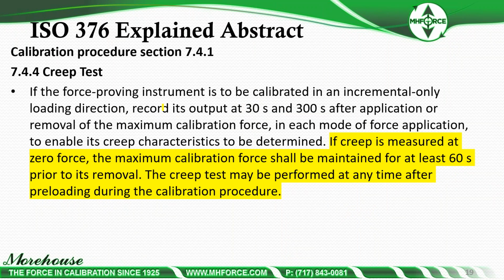Creep test. If the force proving instrument is to be calibrated in incremental loading direction only, so if we're not doing reversibility, we're not doing the X4 and X6 calibration, six sets of data really, we're going to have to do a creep test. And to do the creep test, we're going to record its output at 30 seconds and 5 minutes, 300 seconds, after application or removal of the maximum calibration force.